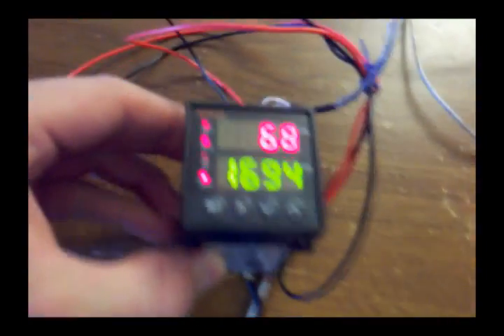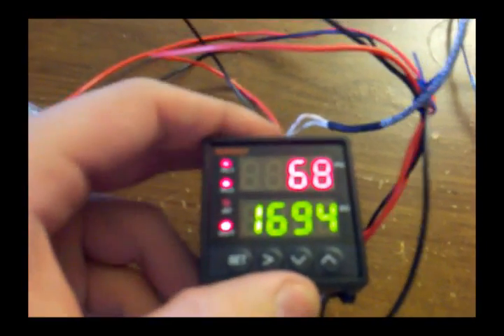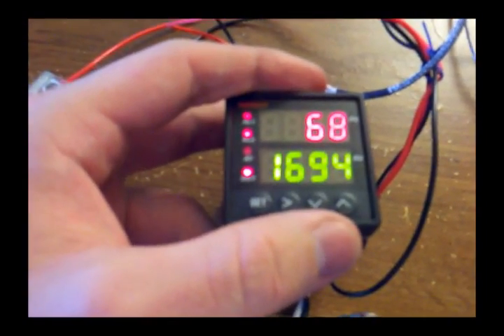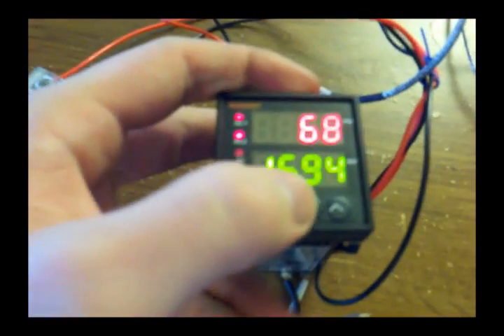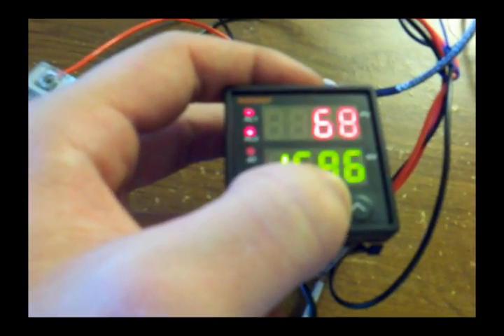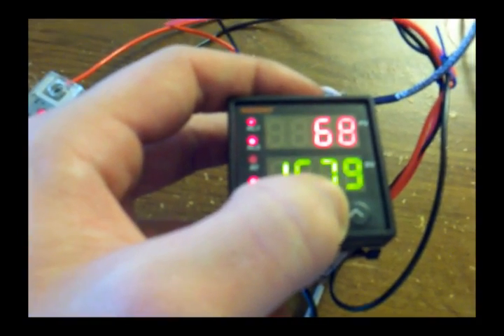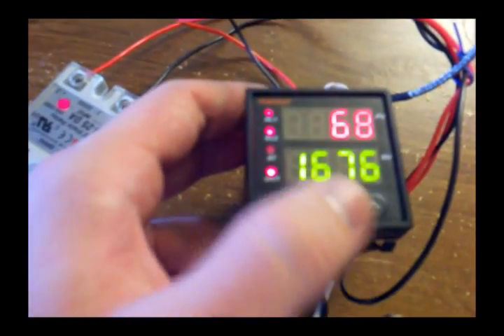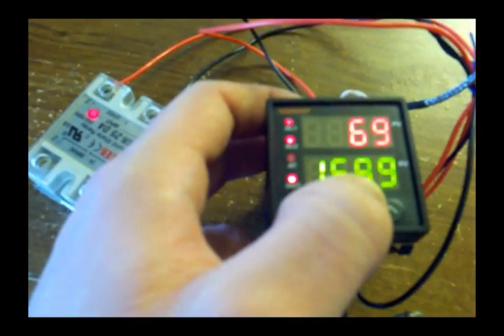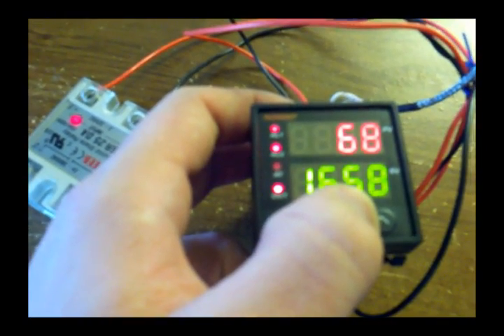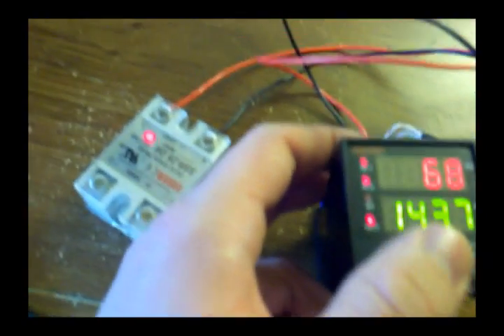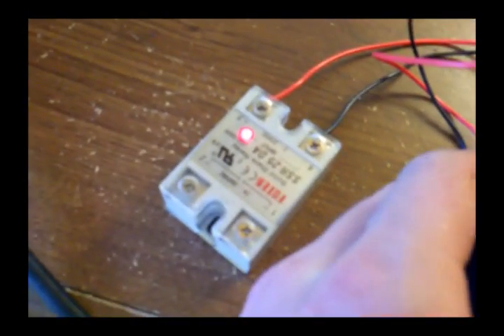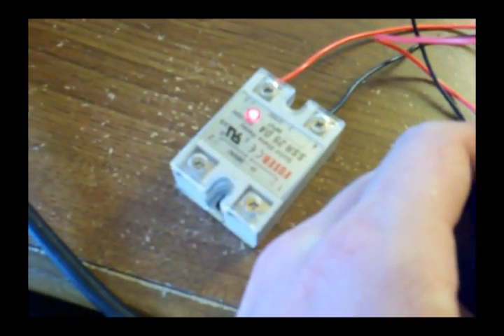So what you see here, the sixty-eight is the process value. That's the actual temperature it's measuring from my room, and the bottom value is the set value. I can tell it to go to whatever I want it to go to. But since it's not connected to my heating element right now, it's not going to matter. But what does matter is if this set value is higher than my measured value, that little light should be on because it should be telling my solid-state relay to allow power from my power source to the heating element.